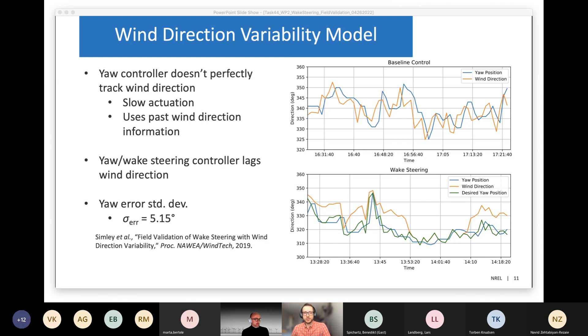One-minute average yaw position and wind direction don't always match — the nacelle position tends to lag behind the wind direction because of slow controller dynamics. So we'll always have some yaw misalignment error. The bottom plot shows what happens with wake steering: instead of tracking the actual wind direction, we're tracking the desired yaw position for wake steering, which is a function of wind direction. The turbine's yaw position will lag behind that target yaw position, and we characterize the yaw tracking error using the standard deviation of the error — we saw a standard deviation of about 5 degrees.